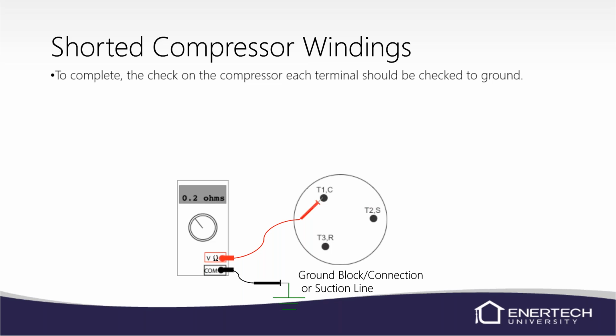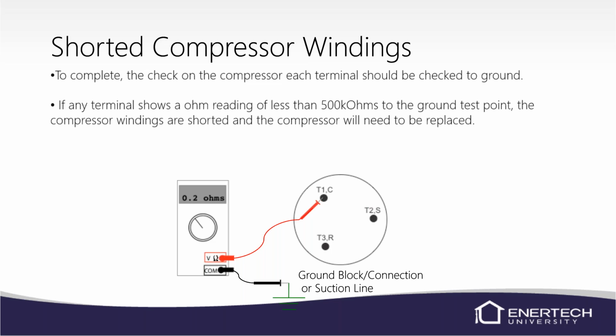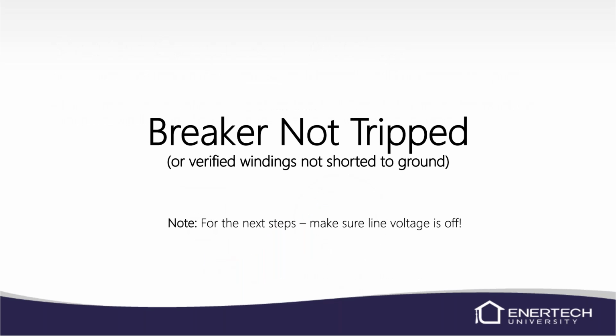Make sure you check each winding to ground, because it could be the start winding is grounded out and not the run winding. So check every terminal, all three of them. If the breaker's not tripped or the windings are not grounded, we'll go ahead and move on, and we're going to leave the line voltage off still.